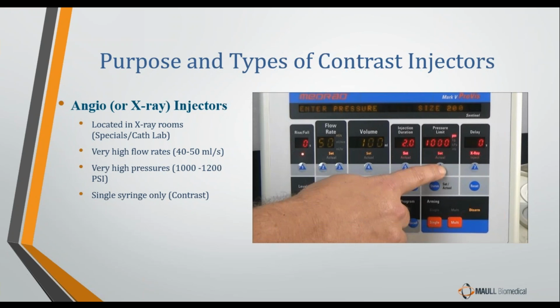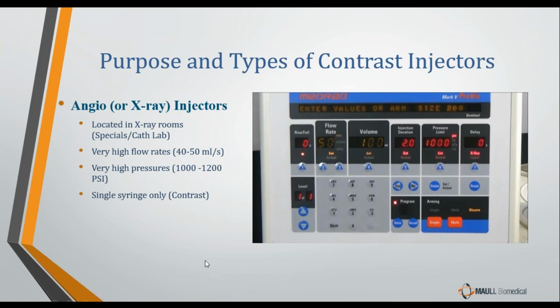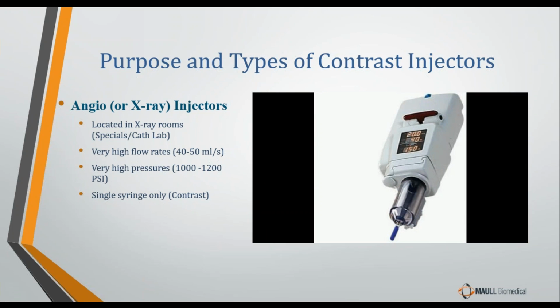So very high pressures, due to the very high flow rates and the very small orifices these contrast fluids are going to be injected through. Now, angiographic injectors are single syringe injectors only. Mark 5 Plus, ProVis, ACIST, Angiomat Illumina here. These are angiographic injectors. They only have one syringe on them. All angiographic injectors, or X-ray injectors, are single syringe injectors, and they're obviously going to be injecting contrast fluid.